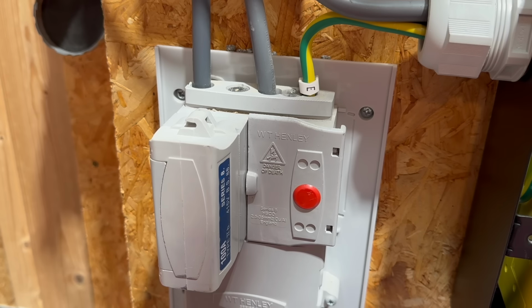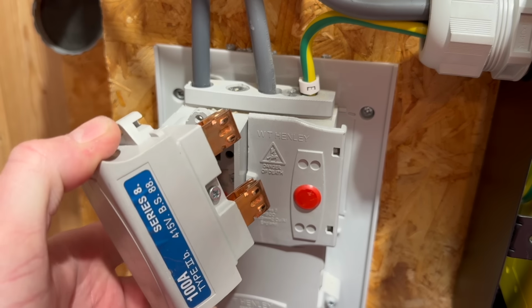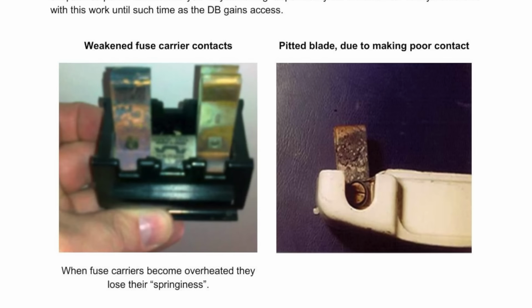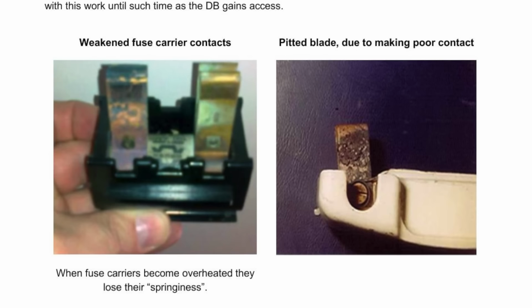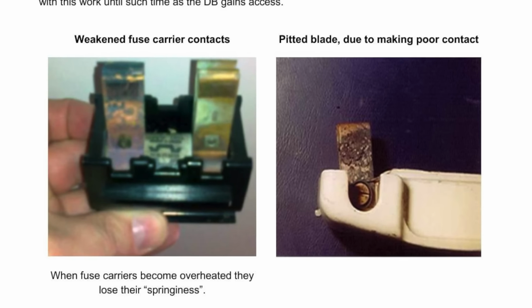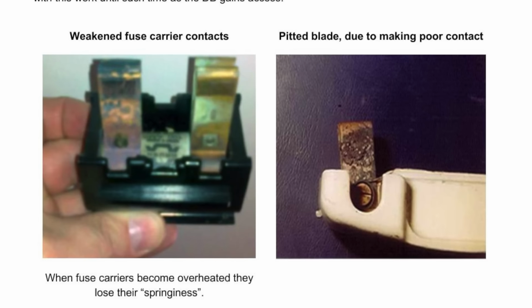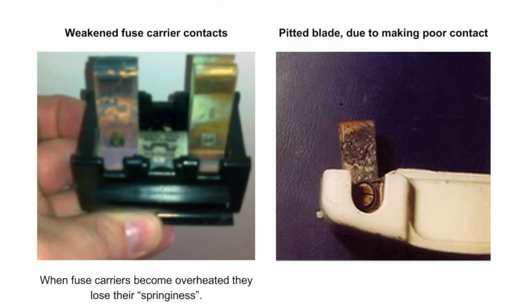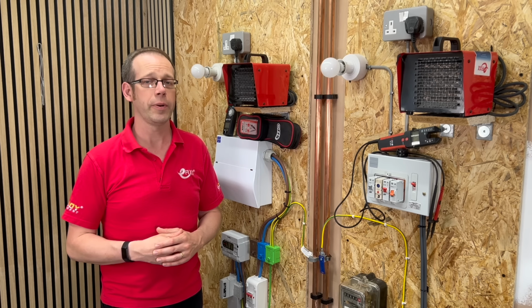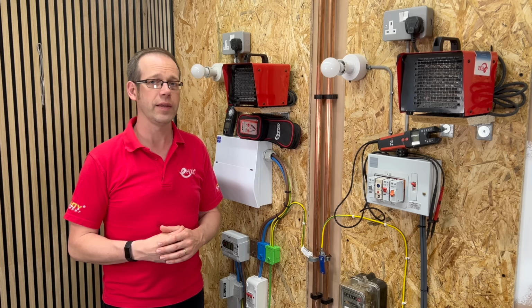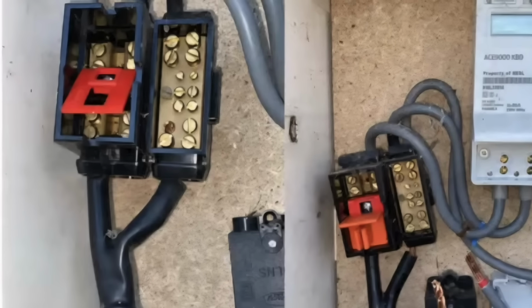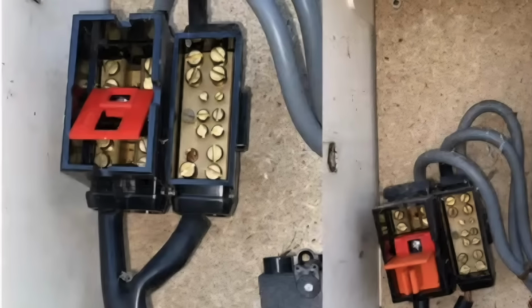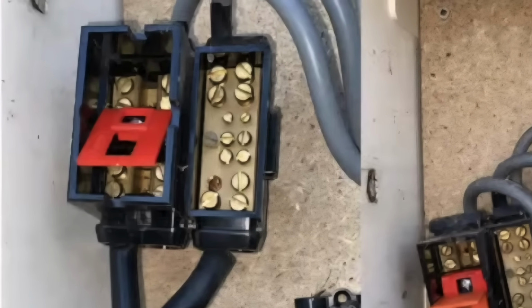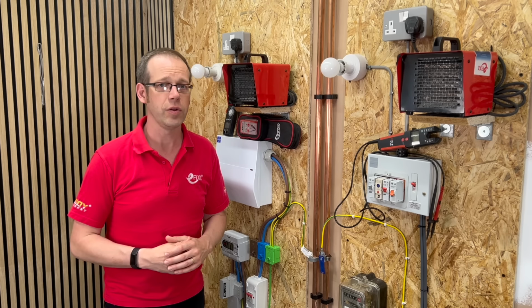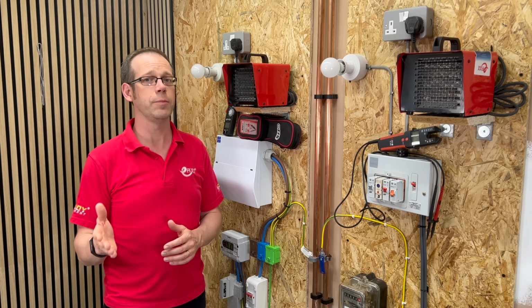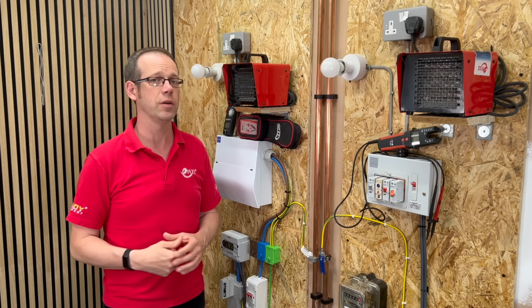The main fuse carrier, often BS88 types, within the service head may show signs of thermal damage due to prolonged overcurrent conditions or loose terminal connections. Cracked or warped fuse holders may no longer provide a safe enclosure for live parts. In some cases, the fuse may be improperly seated, allowing arcing to occur if the assembly is disturbed. It's not uncommon for cracked fuse holders to dislodge when disturbed, especially during meter changeovers or when installing isolators. A live fuse making a poor connection within the service head presents an obvious risk of electrocution or fire.